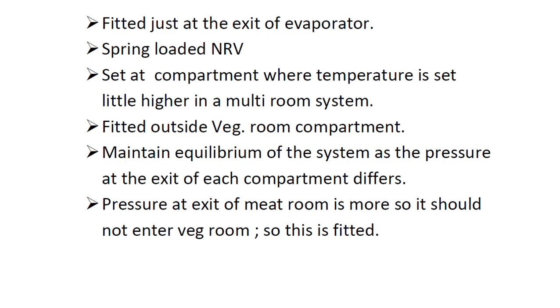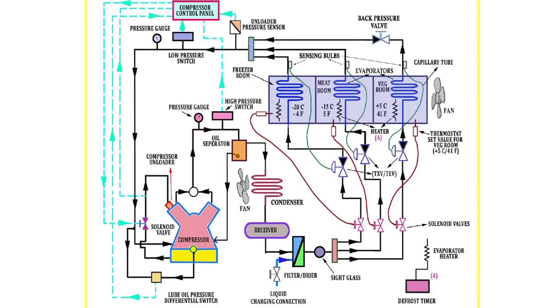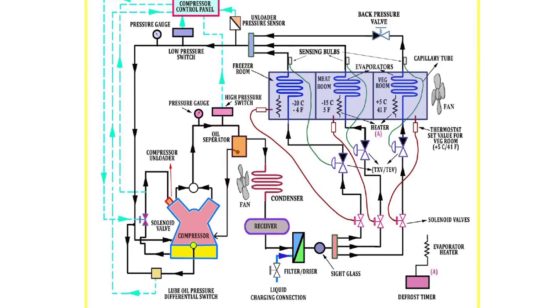The basic function is to ensure that refrigerant does not enter from the meat room into the veg room. It is a spring-loaded valve located at the exit of the evaporator of the compartment that is at a higher temperature — the veg room — fitted to maintain the equilibrium because pressure at the exit of the meat room is higher and should not enter the veg room.